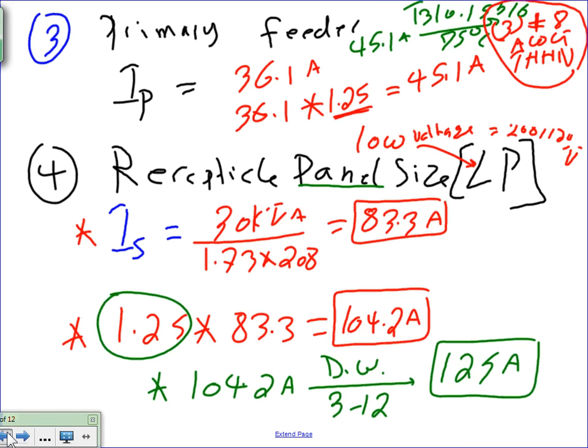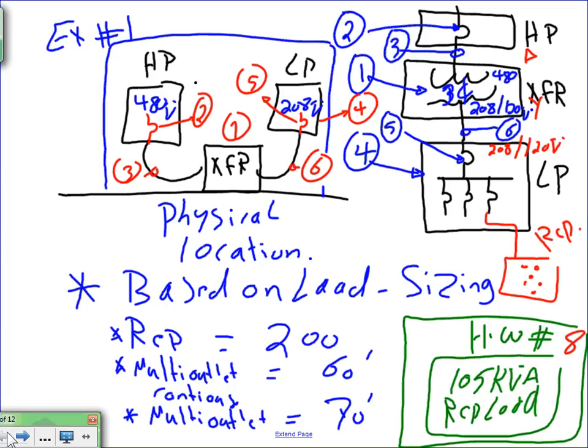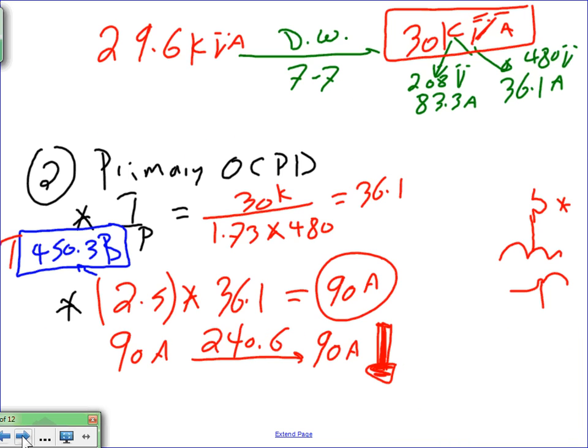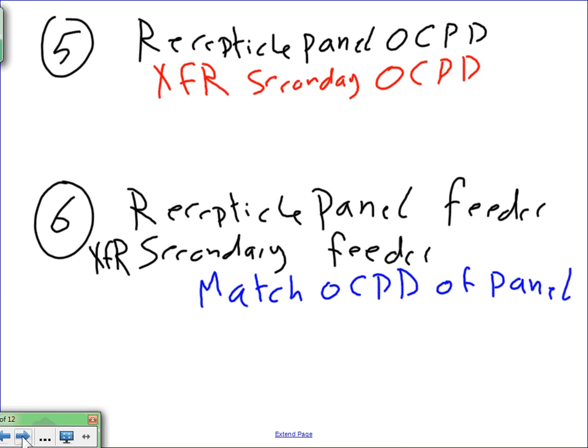Let's pick that one right here. Can you guys see this baby here has two functions? That's the main for the panel and also could be considered the secondary for the transformer. Can you guys see that? Really, technically, the secondary protection for the transformer has to be right in here, guys, right? But we're assuming we have both primary and secondary protection for this transformer. So we'll leave it at this. Receptacle overcurrent protection device.